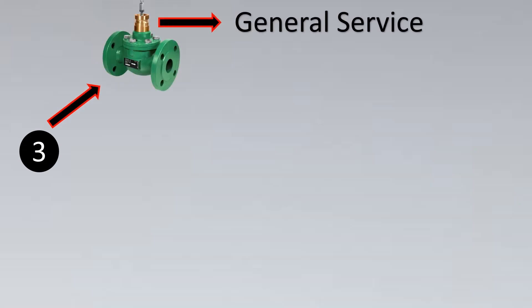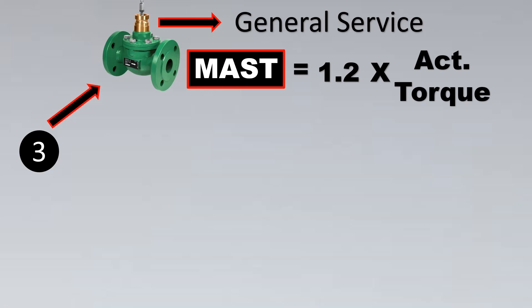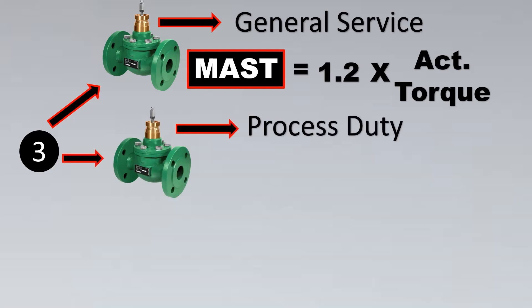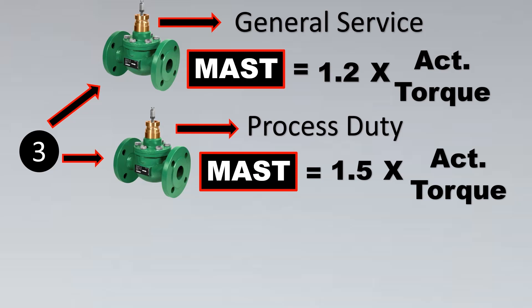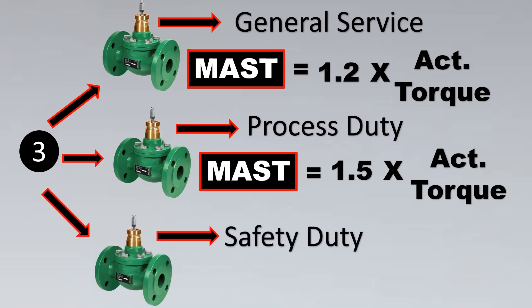The first point is when the valve is just put into general service. As a thumb rule, MAST should be around 1.2 times the actuator torque when the valve is in general service. But if it's used for heavy process duty like blowdown, the MAST may go up to 1.5 times the actuator torque.